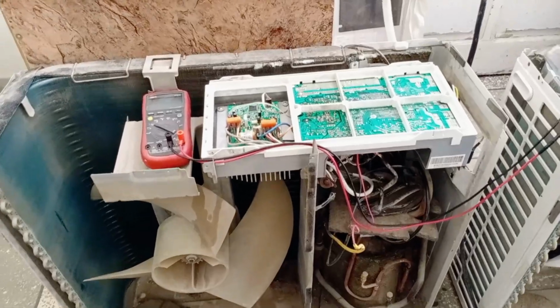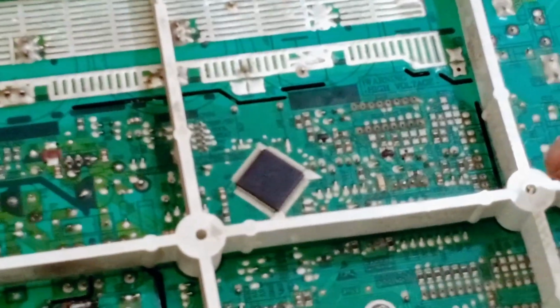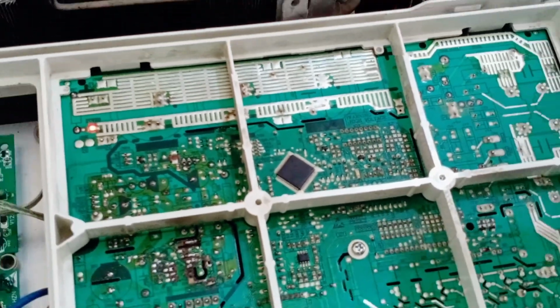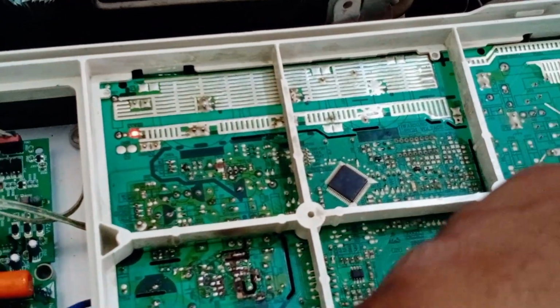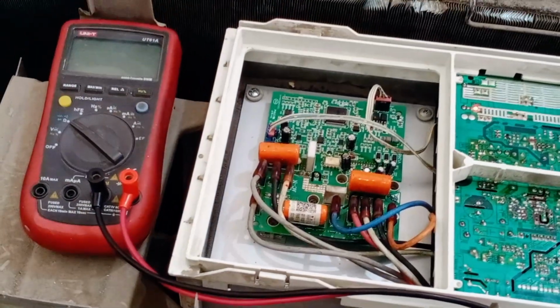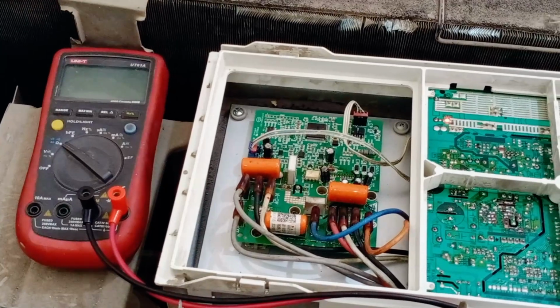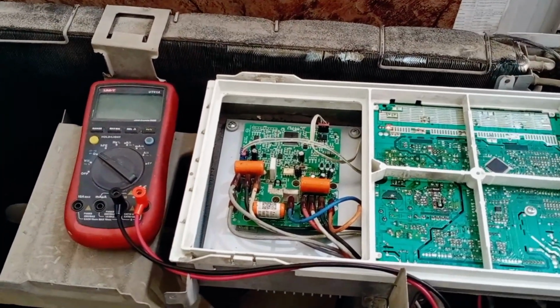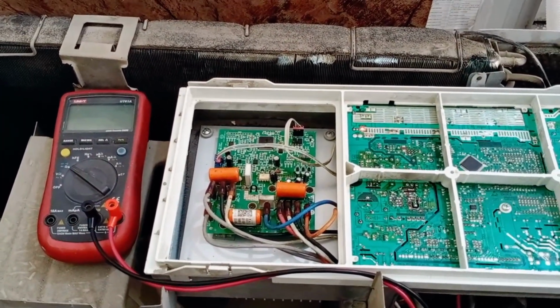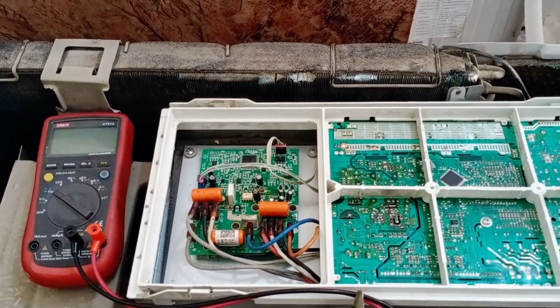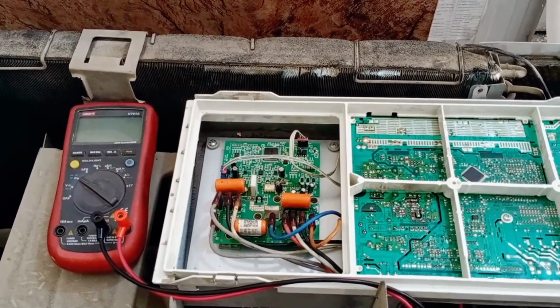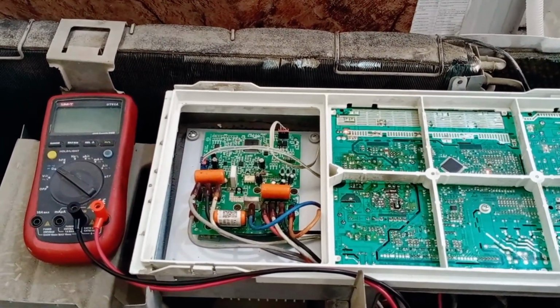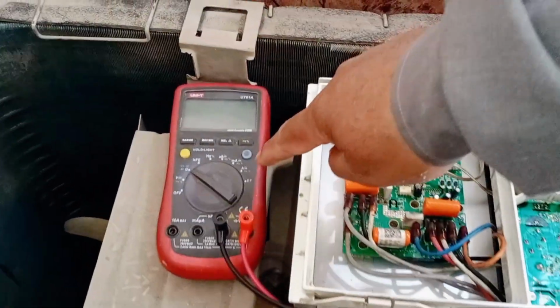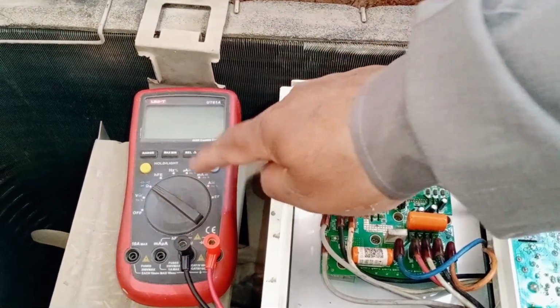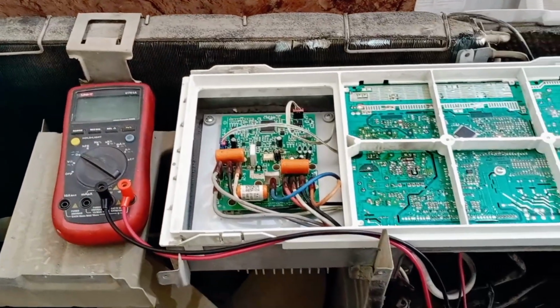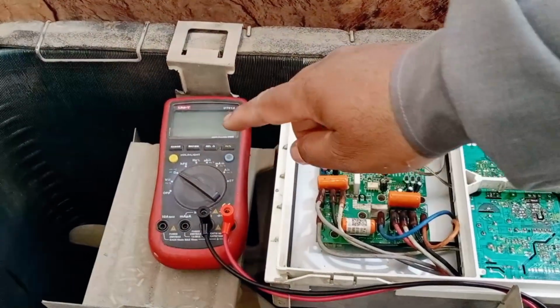The unit has now entered a strange situation. At this moment, the power LED on the circuit board isn't working. It's completely off. However, after a short while, it will turn on again. The compressor will try to start again, and it might also show an error afterward. But for now, the circuit board hasn't reached that point. The purpose of this video is to show that if you encounter such a situation, you should not attach the compressor to the PCB. Always use a high-quality multimeter, because if you have a low-quality multimeter, it won't give you accurate readings, making it difficult to identify faults.